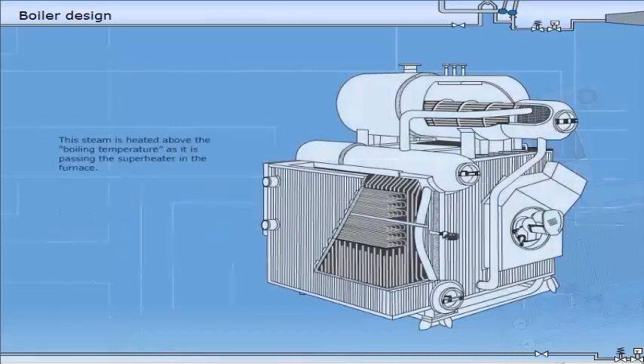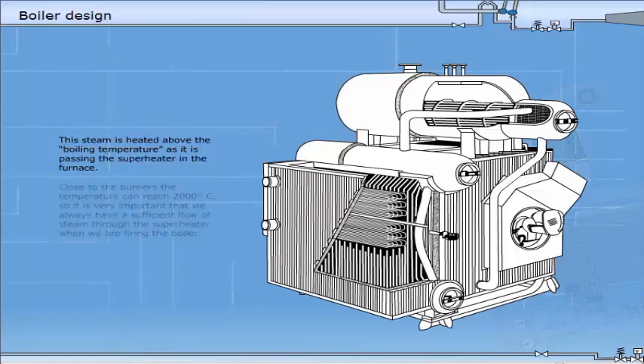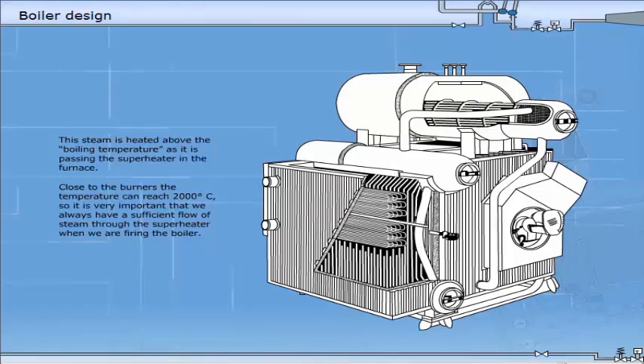This steam is heated above boiling temperature and is passing the superheater in the furnace. Close to the burners, the temperature can reach 2000 degrees centigrade. So it is very important that we always have a sufficient flow of steam through the superheater when we are firing the boiler.